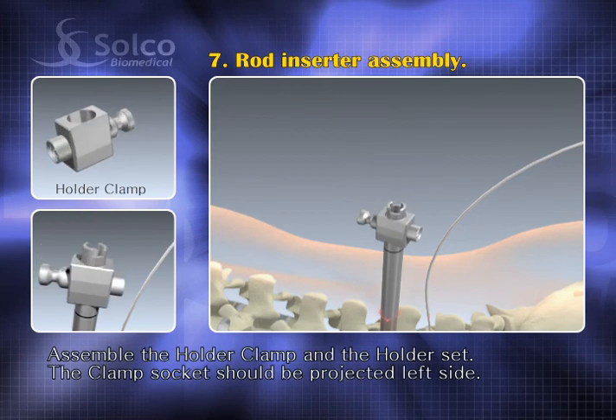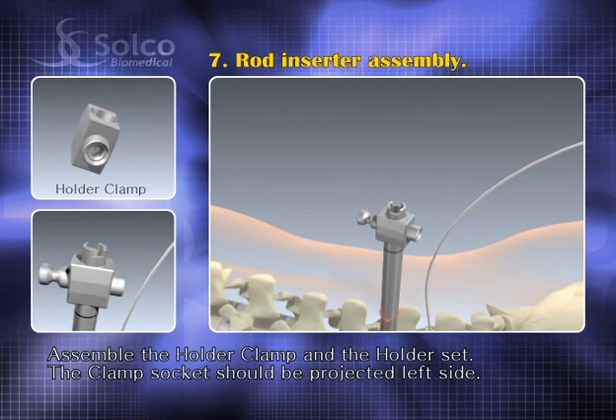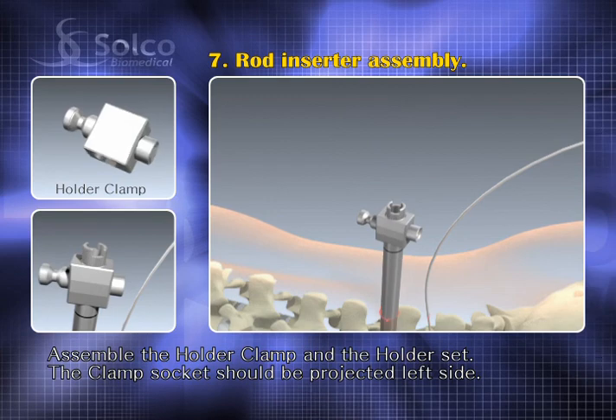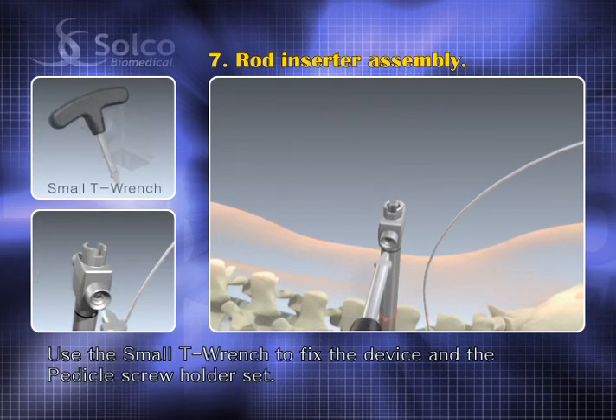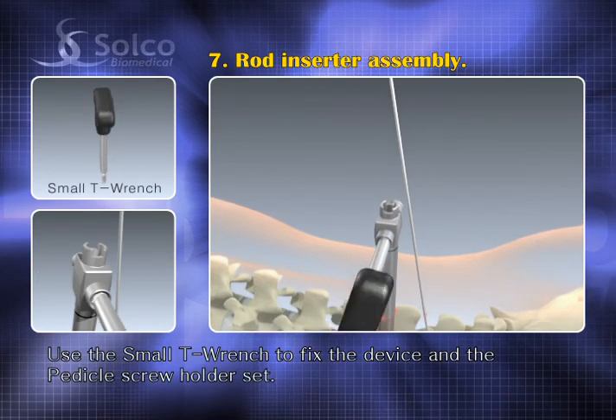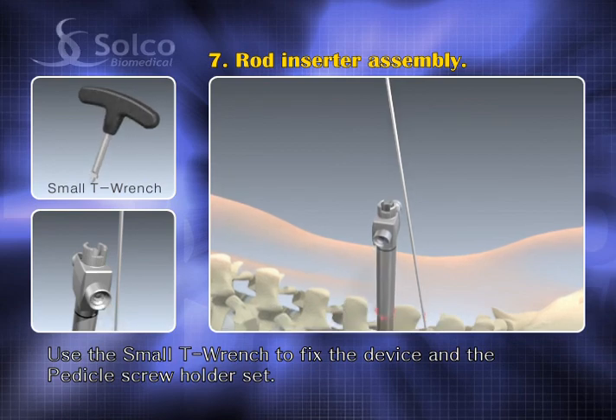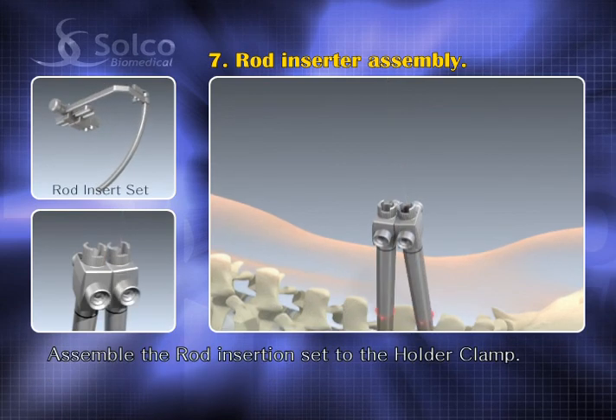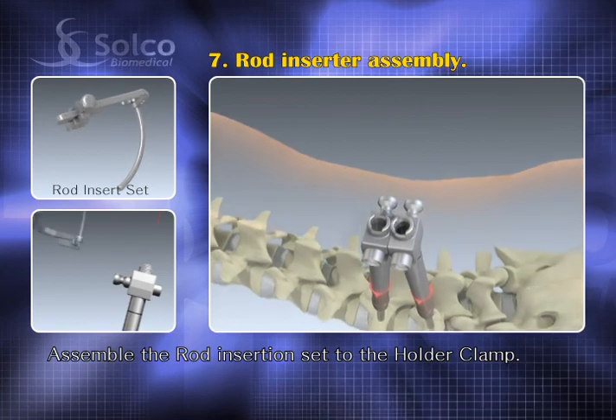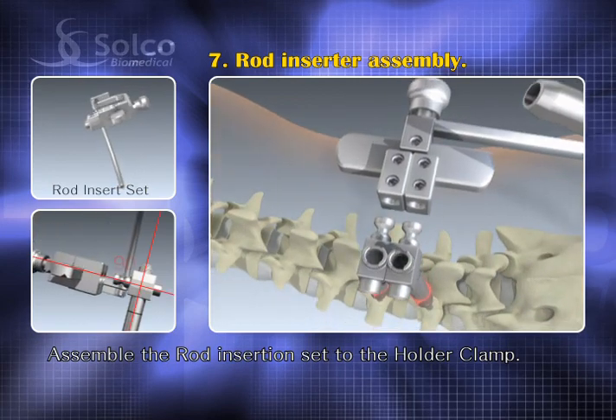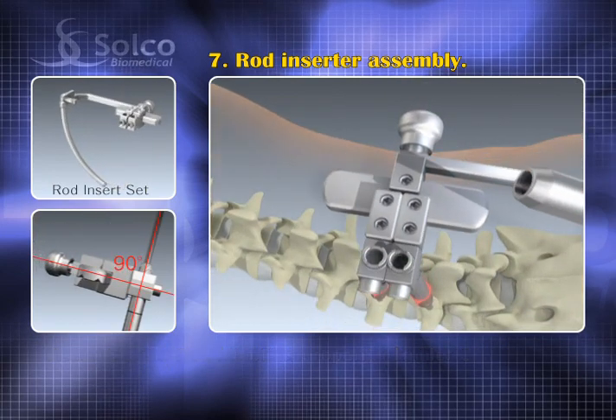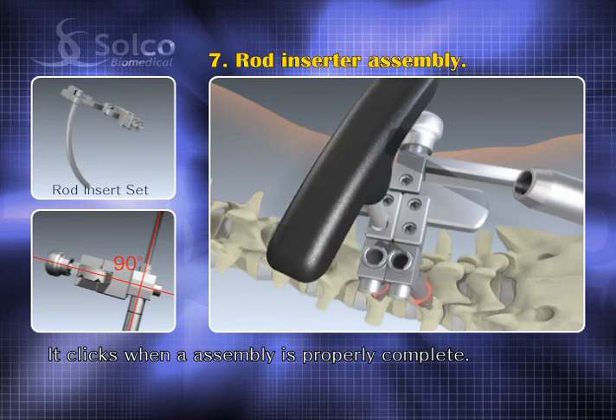Assemble the holder clamp over the holder set and place the projected socket of the clamp. The small T-wrench fixes the device to the pedicle screw holder set. Assemble the rod insertion set to the holder clamp and engage its socket to the clamp; it clicks when assembly is properly complete.